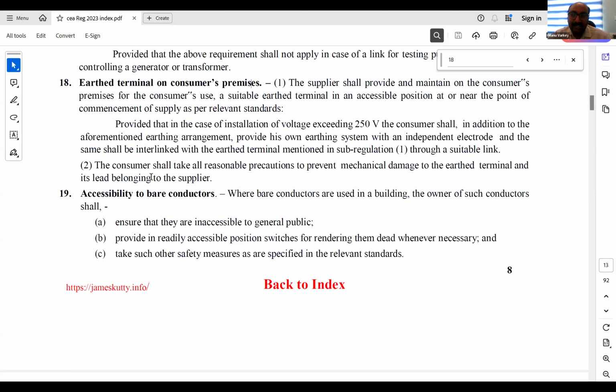a fault occurring on the high voltage side at the supplier's substation should not cause a dangerous overvoltage on the consumer installation. Since in our country most of the installations are rural installations, where the ground potential rise on account of an earth fault is going to be very high, if you are linking the neutral to the body earthing of the supplier, then the consumer installation will be subjected to a dangerous overvoltage. So if the supplier is not segregating his neutral earthing from the body earthing that he utilizes for his substation equipment, then it creates a dangerous situation for the consumer. So that is the issue that we are facing in this regulation especially.